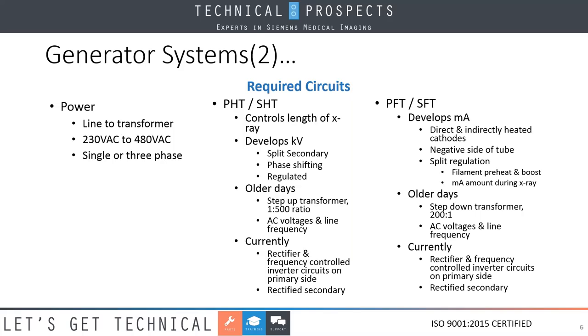When we look at regulation, filament preheat and boost is a separate form of regulation because that is done prior to the X-ray. MA, we regulate during the X-ray. We may use similar circuitry. However, the input to that circuitry is going to be determined by where in the system we are in terms of generating the X-ray. In our older days, our systems basically used a 200-to-1 step-down transformer. And again, these were tied to the AC voltages coming in and also our line frequency. Currently, we use rectifier and frequency-controlled inverter circuits on the primary side, again, with a rectified secondary.